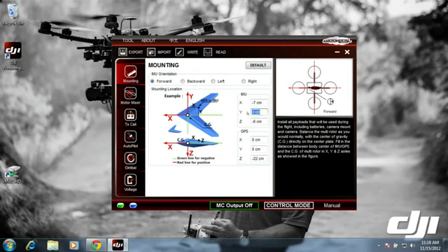If I highlight this and say 10, but then I hit read, it's going to read my current configuration off my master controller. So when I read, it changes it back to what my settings are in the master controller. So that's how write and read work.